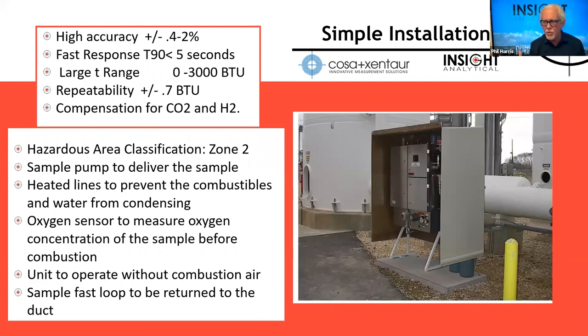It's available as a zone 2 device, so we can put it in a hazardous area. If there's low pressure fuels, we can use a pump to deliver samples. Heated lines keep the combustibles and water from condensing on the lines. Our oxygen sensor measures the oxygen concentration of the sample before combustion. So if there's oxygen in your fuel, it's going to bias our numbers, because remember, we're looking for how much more oxygen we need to add. So we can add an oxygen sensor and say, well, how much oxygen is in the fuel? And that way we can get you to the right air demand for the burner.